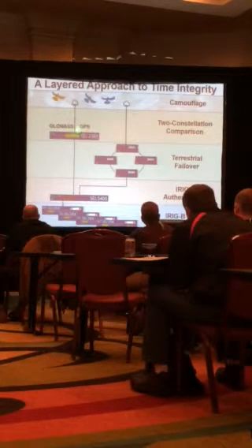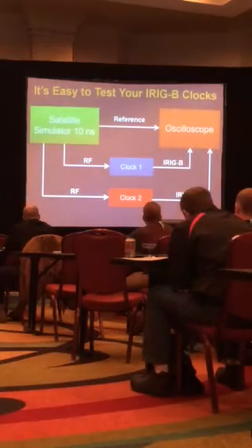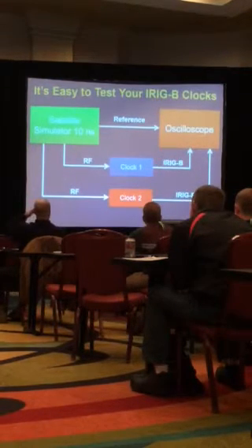So here's a GPS clock, and the satellites are hidden. Here's a terrestrial system. The ICON network will distribute precise time within tens of nanoseconds. And if you do lose GPS, everybody on that network still thinks it's the same time to the nanoseconds, and that's good. So we talked about the IRIG authentication, and then the IEDs, the relays themselves, do a quality check. So it's real easy to test clocks accurately.